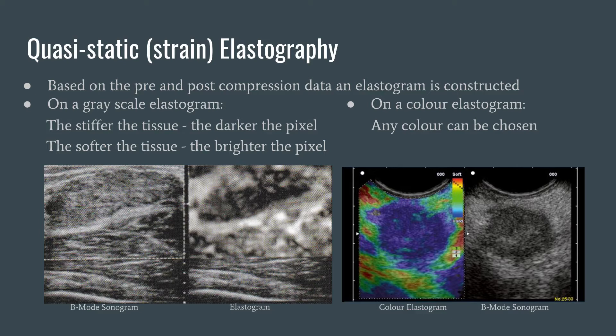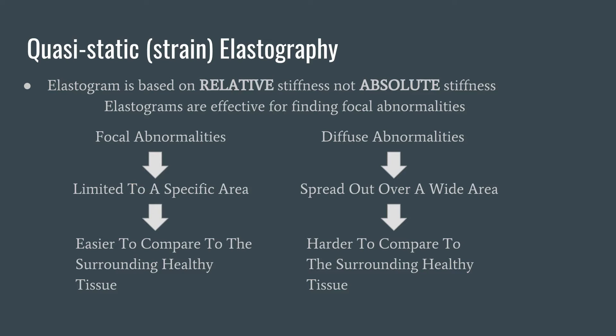The elastogram can be displayed side by side with the sonogram, and stiffer tissues will be darker and softer tissues will be brighter. It can also be a color image overlaid on top of our 2D image. You can use any color you want, but the default color for stiff tissues for most machines appears to be blue. Of course, this is all based on relative stiffness. If a lesion, which is very stiff, covers the entire elastogram, we wouldn't know any better — we would just think it's normal.